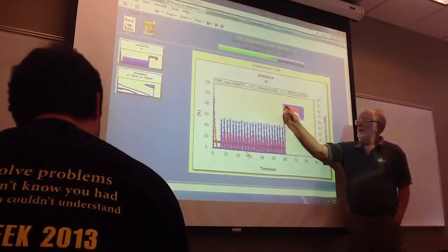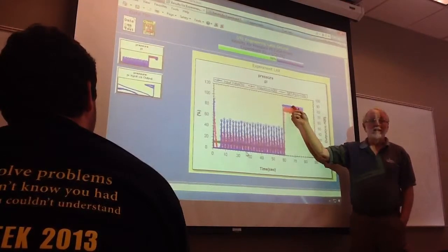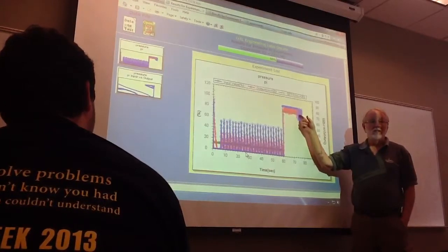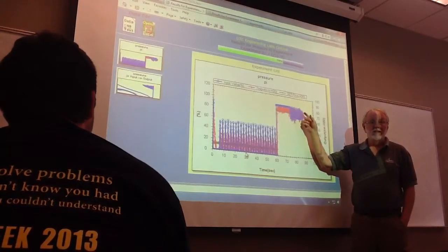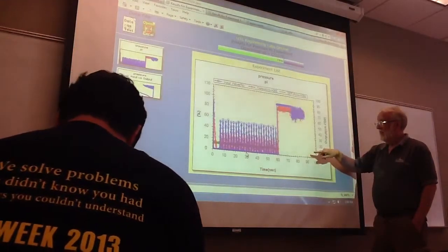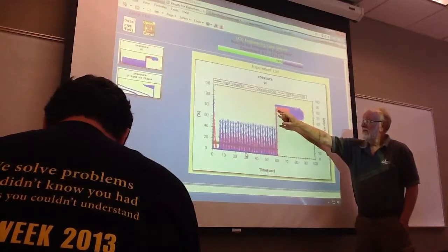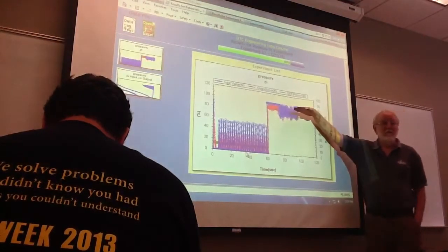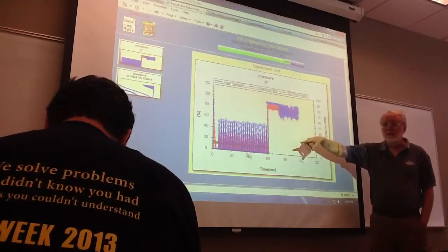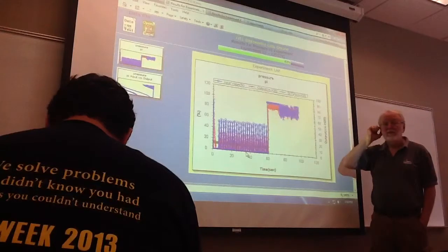That's reset wind up. It stayed there for about 10 seconds, pegged, before it came down and started doing some control again. The way I got this to happen was to make the delta R very close to the maximum of the operating range. My delta R was 65, wasn't it?